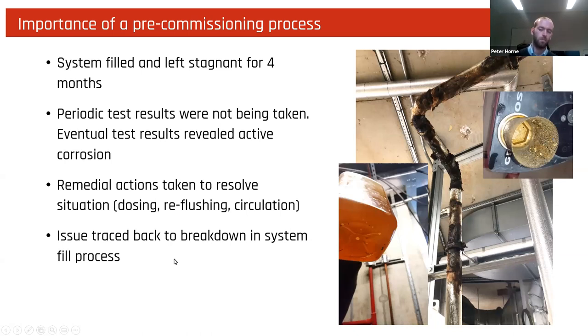Here's an example of what happens if we don't have a pre-commissioning process in place. This was a site that we visited. We did find out almost immediately that the system was filled and then left stagnant for 4 months. Periodic testing had not been taken throughout the ongoing process, and there were significant remedial actions required, which incurred very high cost. Reflushing, biocide dosing, lots of attention to maintain circulation, strainer cleaning, all primarily because there was a breakdown in the process from the outset.